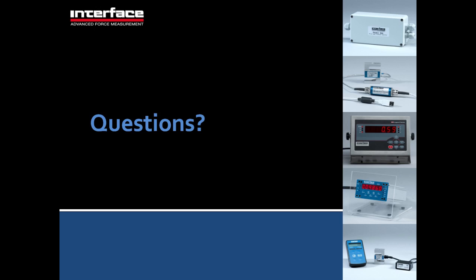They could be scaled. For example, with a signal conditioner, we could apply a known 3 millivolt per volt signal and then scale it for 10 volts. People don't typically send instruments in for that, though. Some instruments, however, especially ones that have TEDS capability or displays like our Model 9840 that actually measure millivolts per volt, do have an internal millivolt per volt calibration. And those instruments should be sent in periodically to be calibrated. They don't necessarily have to be, though, if the customer is able to apply a load to their load cell and then scale the instrument themselves.